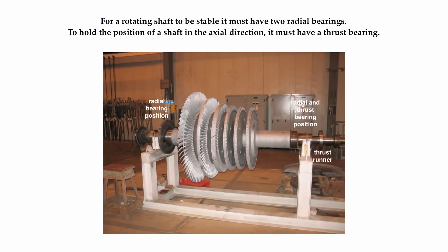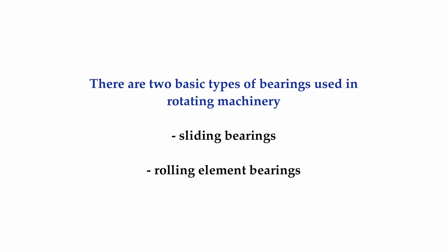Shown here is a rotor from a steam turbine. A rotor consists of a shaft and rotating parts attached to it, like blading, impellers, or an armature. One of the basic design principles is that for a rotating shaft to be stable, it must have two radial bearings. Radial bearings maintain the center line of the shaft on a fixed axis of rotation. A thrust bearing prevents the shaft from moving in an axial direction so the rotating part doesn't touch a stationary part.